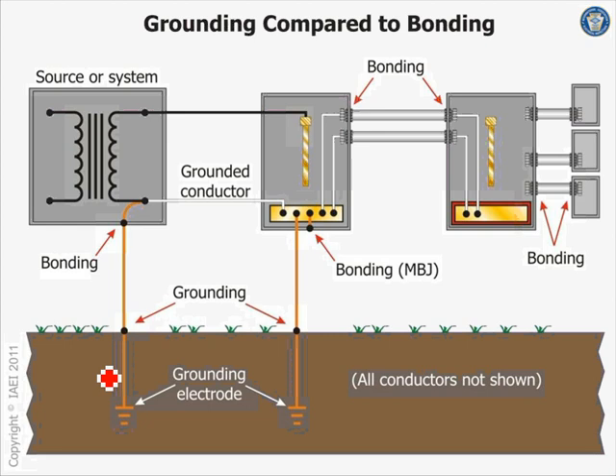When I come from here, the supply side bonding jumper, you guys remember the supply side bonding jumper here? It's uniquely bonding. System bonding jumper, uniquely bonding versus grounding. Equipment bonding jumper on the load side, equipment bonding jumper on the load side.